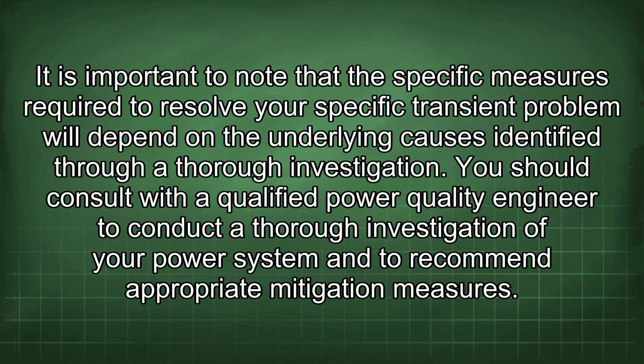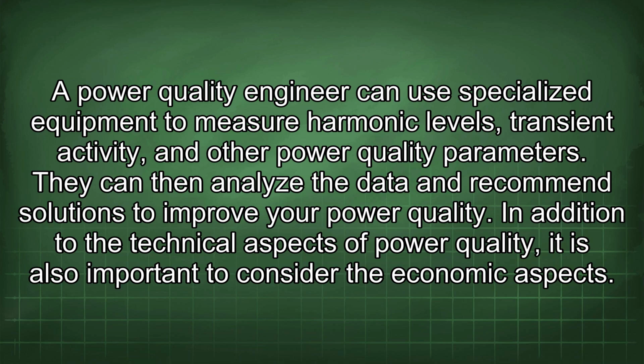It is important to note that the specific measures required to resolve your specific transient problem will depend on the underlying causes identified through a thorough investigation. You should consult with a qualified power quality engineer to conduct a thorough investigation of your power system and to recommend appropriate mitigation measures. A power quality engineer can use specialized equipment to measure harmonic levels, transient activity, and other power quality parameters. They can then analyze the data and recommend solutions to improve your power quality.